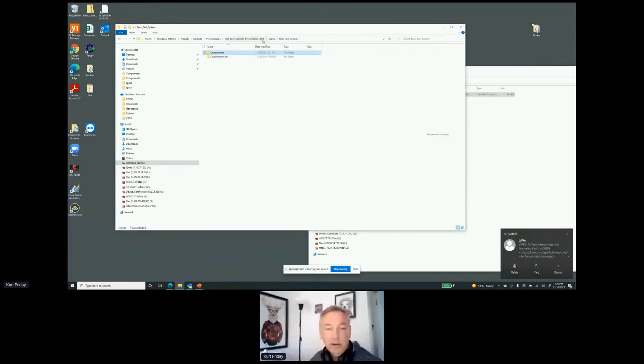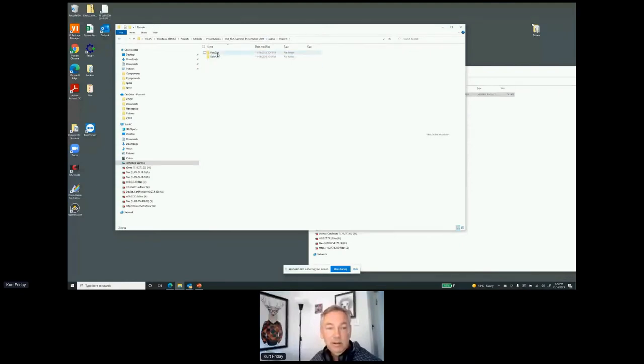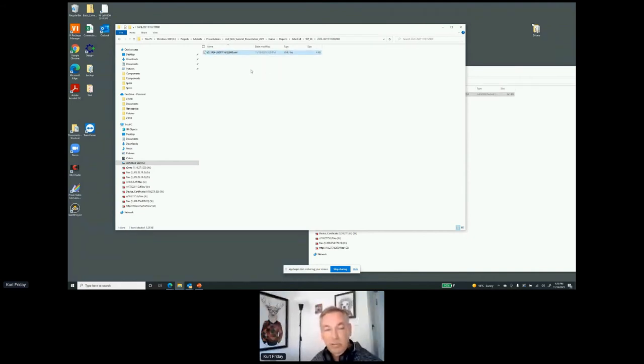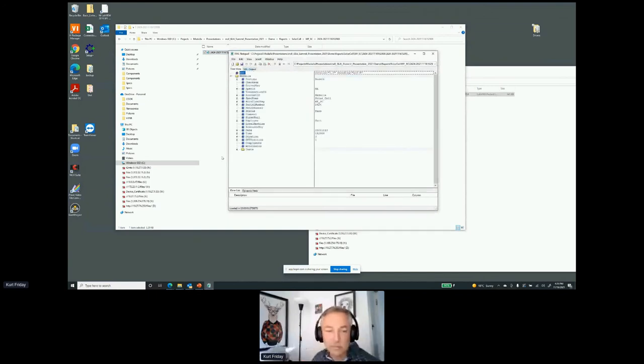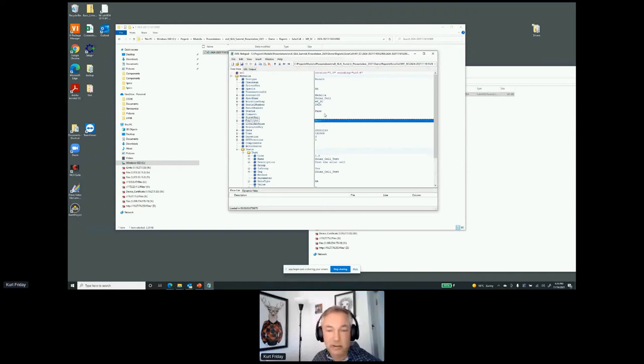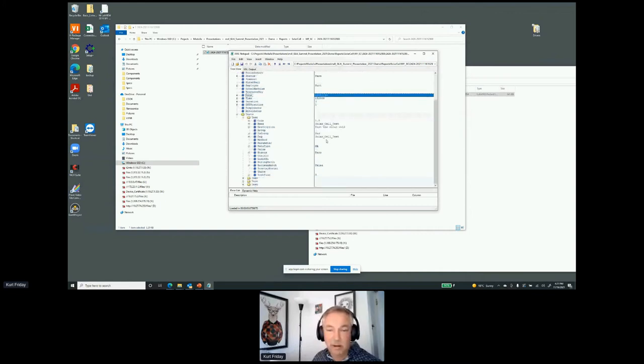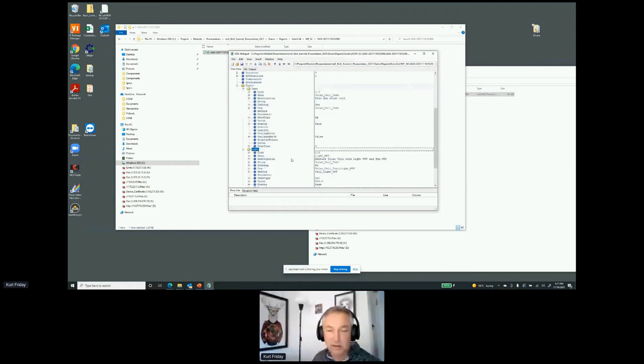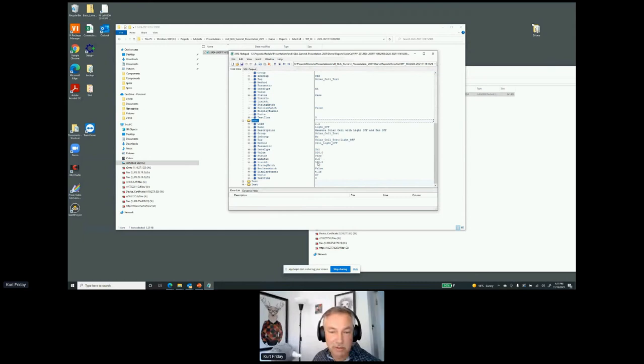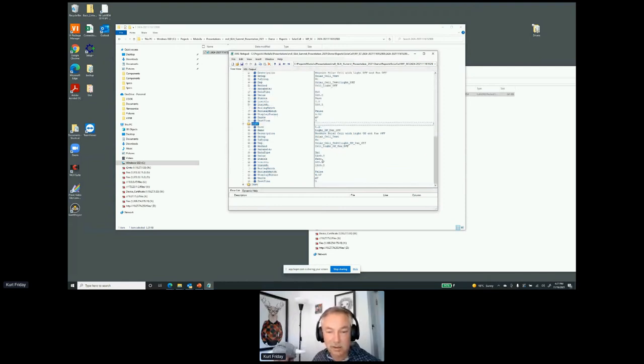Looking at the reports — there are a few of them here. Opening one up, you can see the header is filled out: who did the test, what was the final result, serial number, date and time, and then the subtests with the value of each test. This was the simulation run — it was a pass, with values of 500 and 1200.